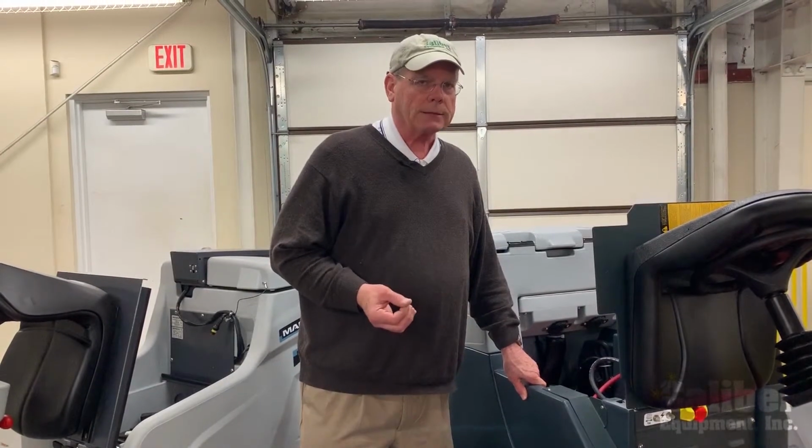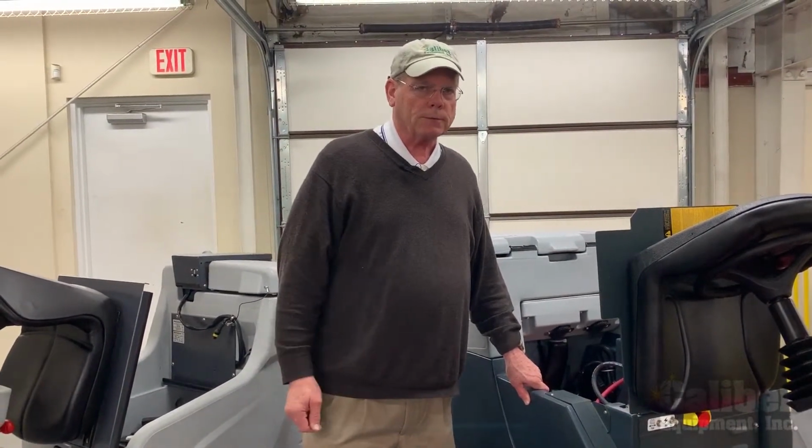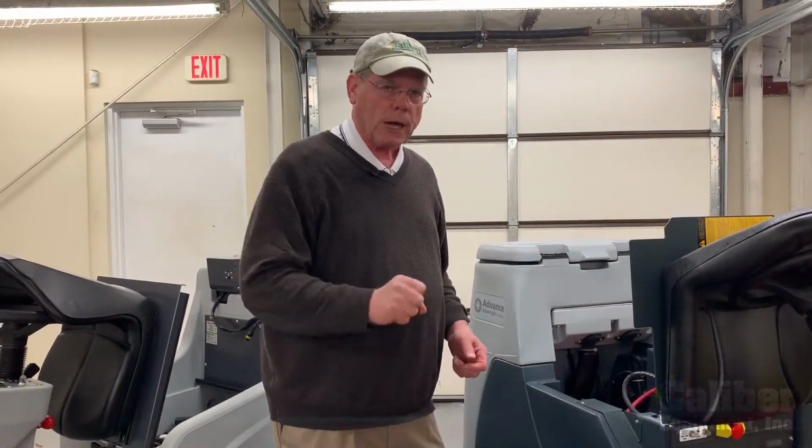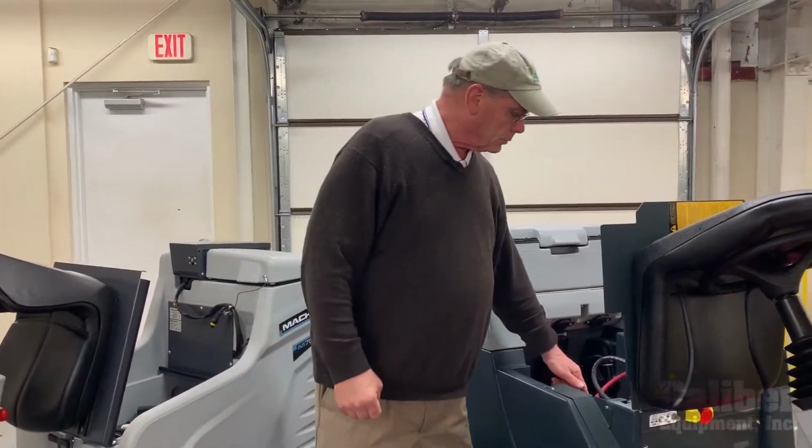But one of the things that will come out of this battery is hydrogen gas. Hydrogen gas is explosive. Think of the dirigibles. We're dealing with a device that can create an electric spark. If I was to take a wrench and I was working on these batteries and I was to cross both the positive and the negative post and connect those two posts, I'm going to get quite a shock, a spark. And that spark alone can generate and ignite hydrogen, which can create an explosive situation.